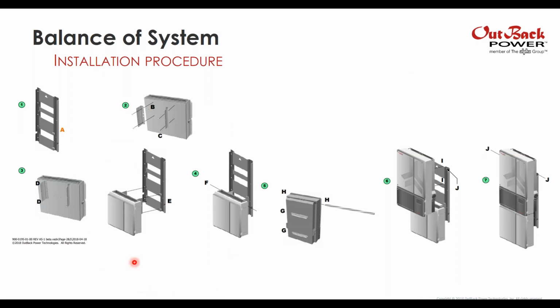So the installation procedure, from the quick start guide: first, hang the mounting bracket. Second, put those fins, or mounting wings, on the back of the box and secure them, then hang the box onto the mounting bracket. We live in earthquake country here in Washington, so you could put retaining bolts into the box. Take your 3/4 inch conduit stub, slide it through the top of the SkyBox, grab a friend to help you hang the SkyBox on the wall, and you can also secure the SkyBox at the top.